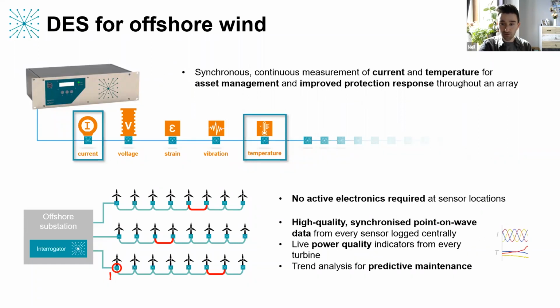So uniquely, because we have all this data coming to a central point at this interrogator, all of a sudden we have access to this high quality synchronized point on wave data from every single turbine in that array. So that allows us to then look at the things that Charlotte was talking about, power quality indicators. And in particular, it means we can have live power quality indicators from every single turbine in the array. So we're no longer looking at the sum of all the power quality that's measured at the offshore substation necessarily, but actually a discriminative view of what's going on in every single turbine. And the combination of the current and the temperature then allows us to start looking at trend analysis and correlations to think about predictive maintenance and planning O&M responses before a fault occurs.